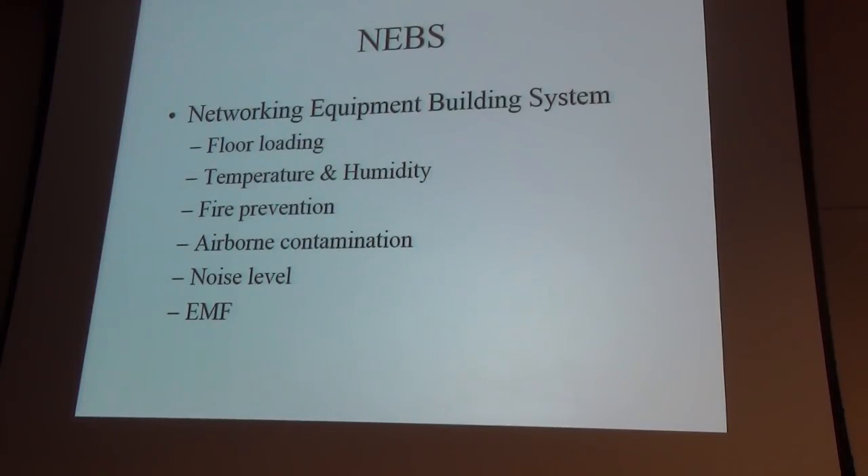Floor loading matters because of heavy servers. Also important is maintaining temperature and humidity. If you look at specs for any server, network gear, or storage gear, you'll see humidity requirements. I've seen places where they couldn't control humidity — in dry parts they brought in humidifiers to prevent static electricity, which is bad. In another part of the year the same site had air conditioning so bad it couldn't draw humidity out, leading to condensation and water droplets on electrical equipment — also bad.